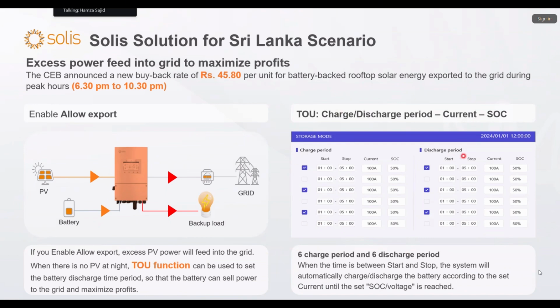So these are the charge period times, and this is going to be the discharge period times in which you can set the power from the battery to the grid. So you can sell the battery power to the grid at night time or in the daytime, whatever slot you put over here. Here is the start, when this period will start, and when you want it to stop, how much current you want drained from the battery to the grid, and what the reachable SOC should be. Similarly, you have 6 periods of discharging and 6 periods of charging. When the time is between start and stop, the system will automatically discharge the battery according to the set current until the set SOC is reached.